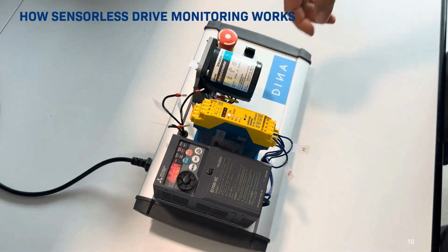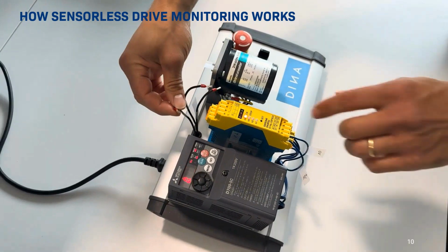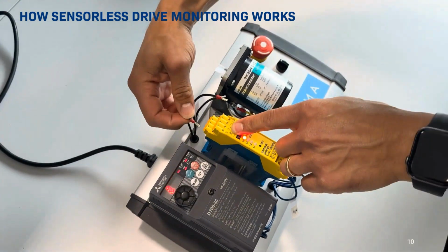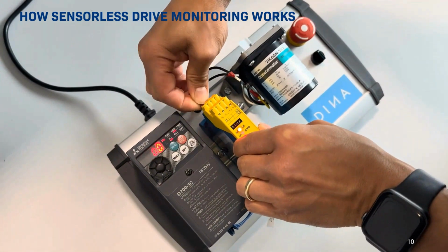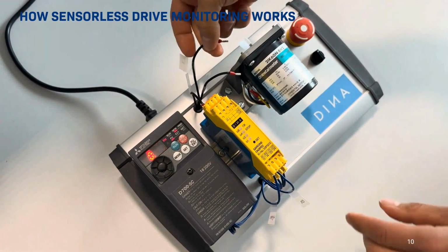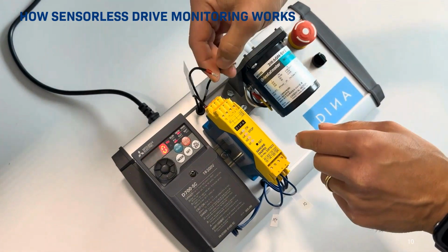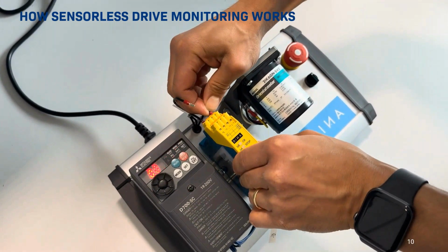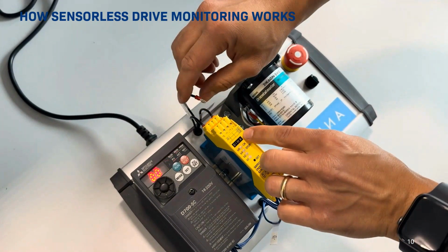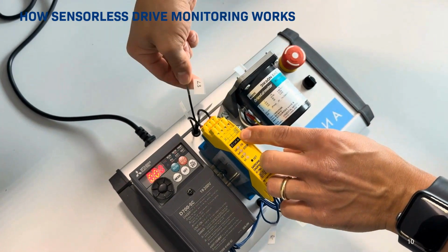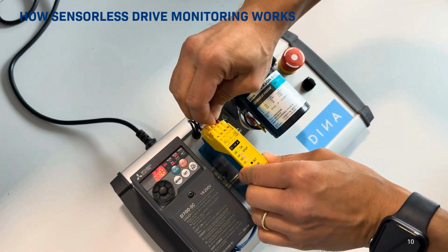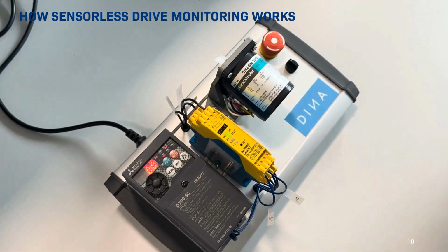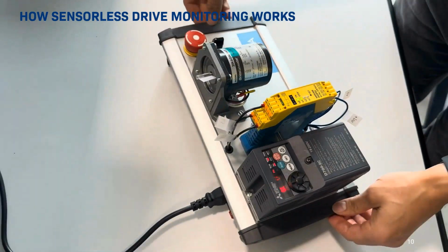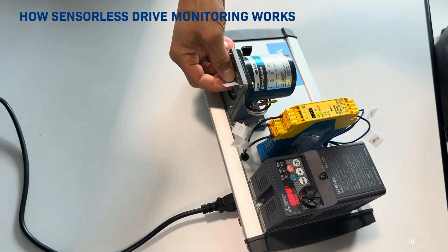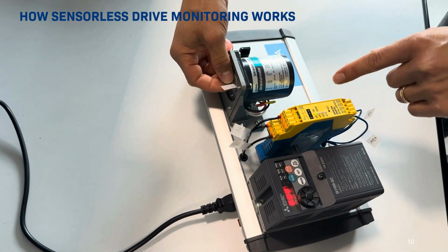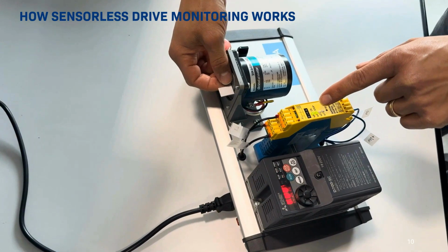To enable the monitoring, you must pick up the 3 signal phases, U, V and W, or L1, L2, L3, that go from the frequency converter to the motor. You connect these phases in parallel directly to the inputs of the sensorless module. This simple method eliminates the need for any external encoder or sensors. As soon as the motor phases are connected, the module immediately begins its monitoring function.